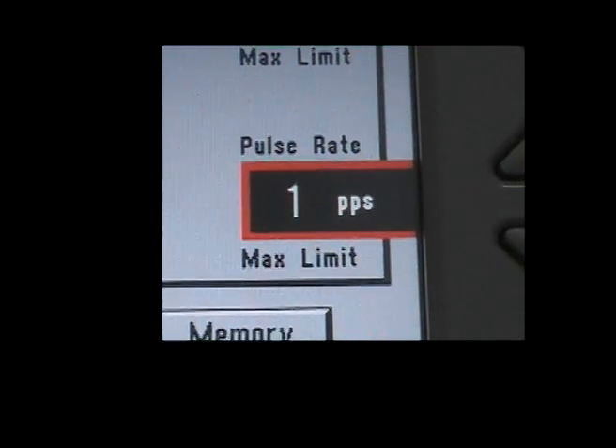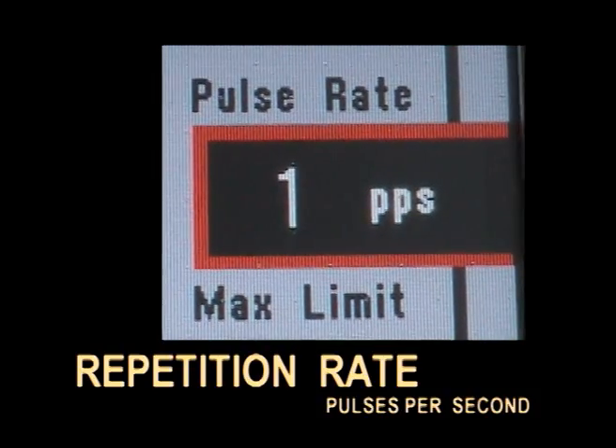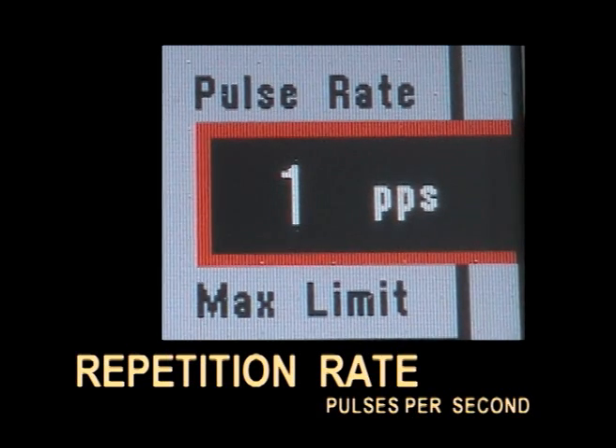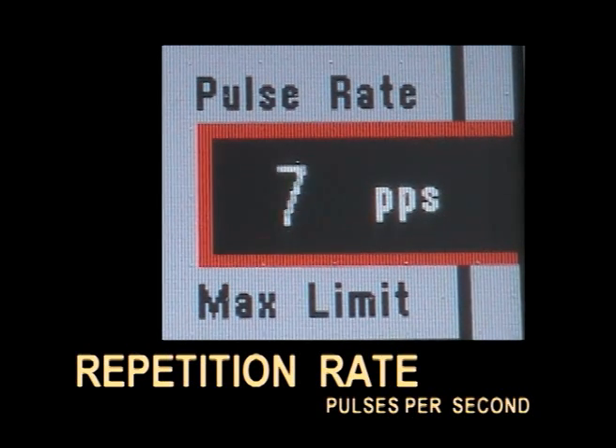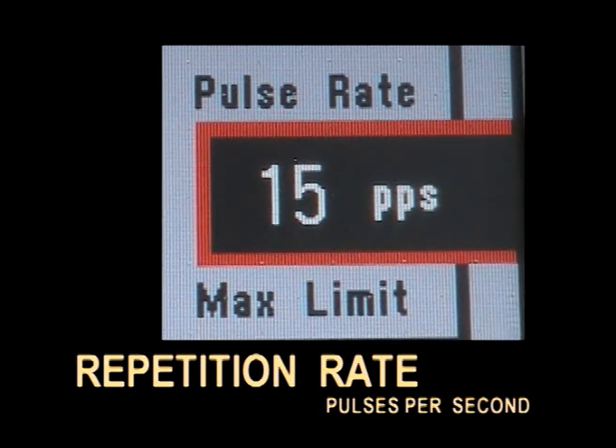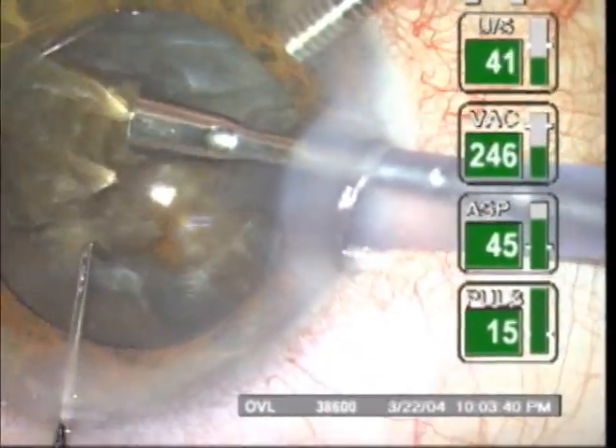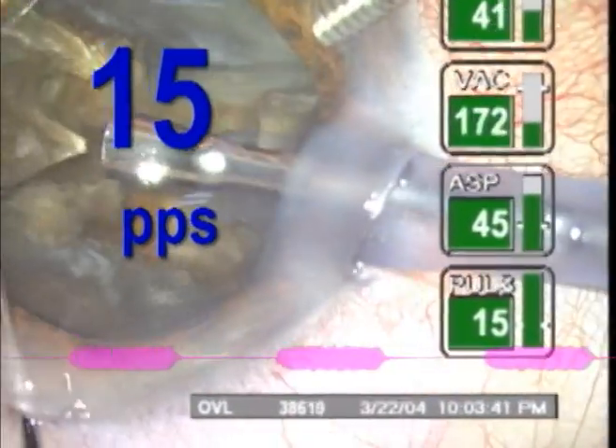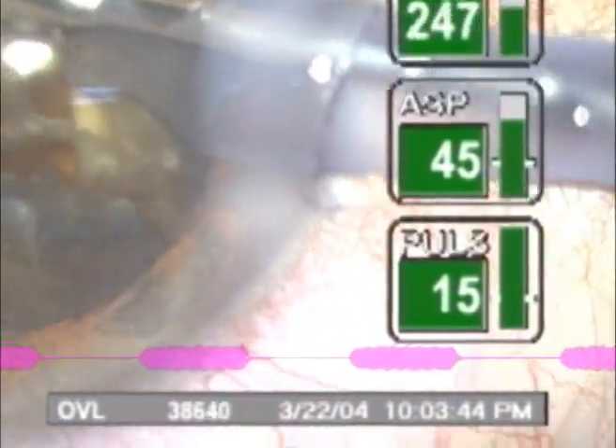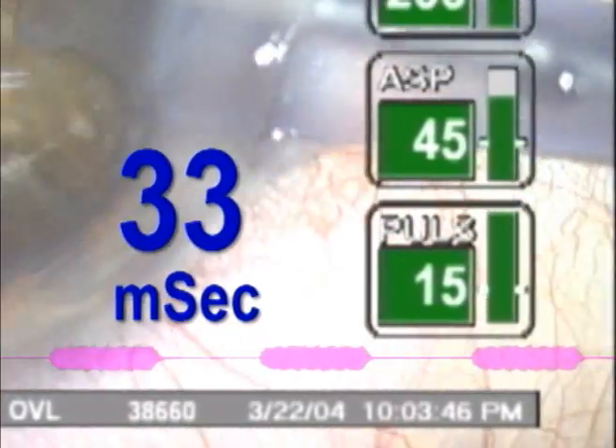The frequency of occurrence of ultrasonic pulses is termed the repetition rate, and is expressed in pulses per second, being typically adjustable between 1 and 15. At maximum repetition rates of 15 pulses per second, the active interval of each cycle is 33 ms.